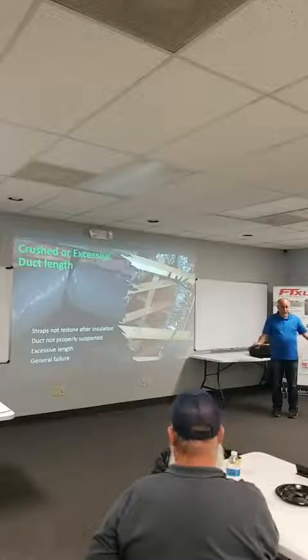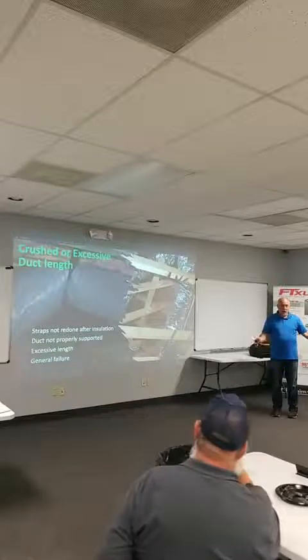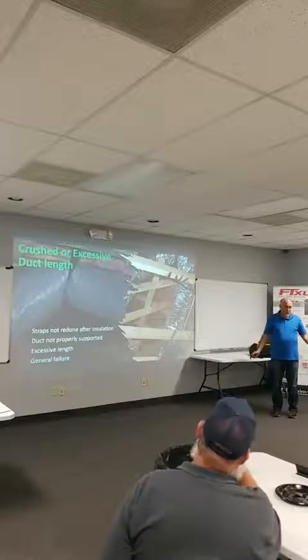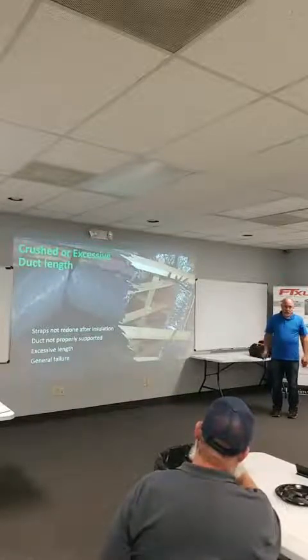This is not a lie, this poor kid. We pulled out, I don't know how many feet of flex duct out of this job, and got the airflows where they should be. And that excessive flex duct length also has a lot of thermal gain with that.